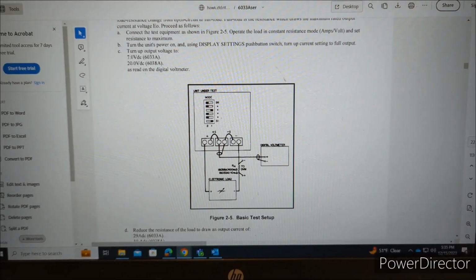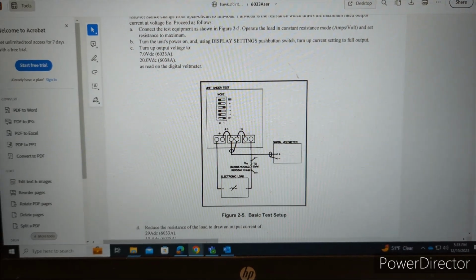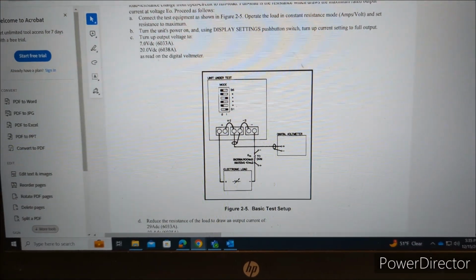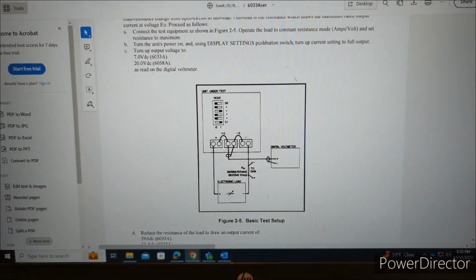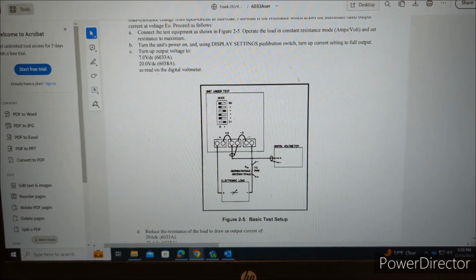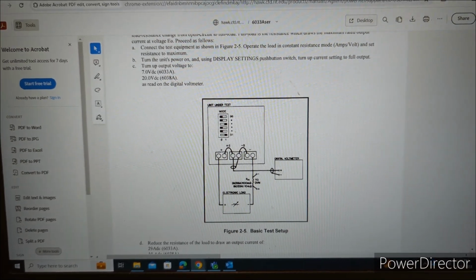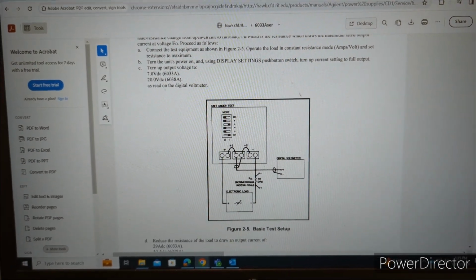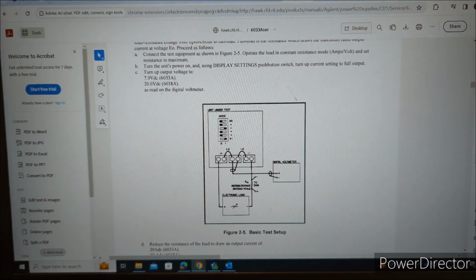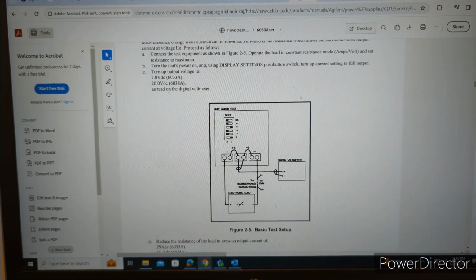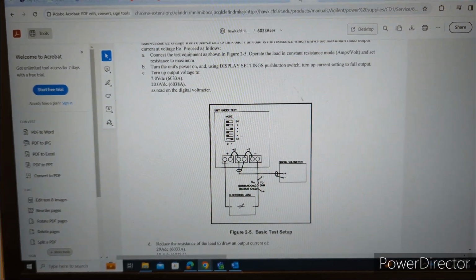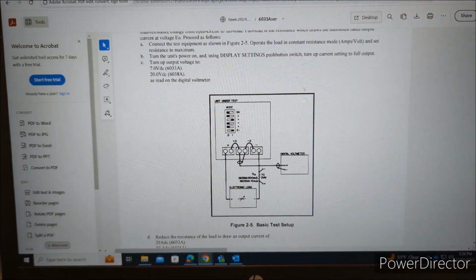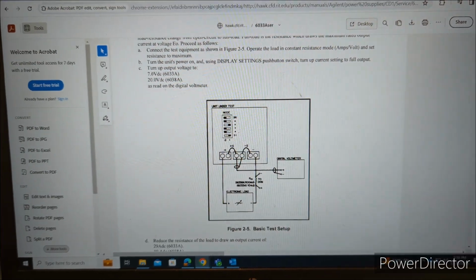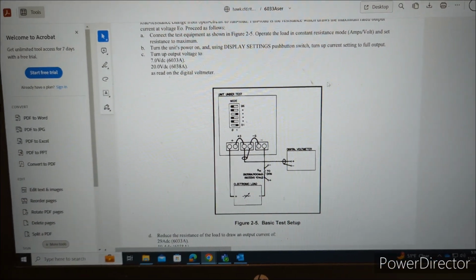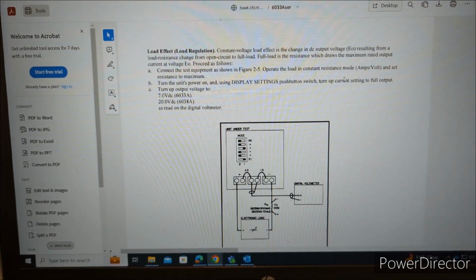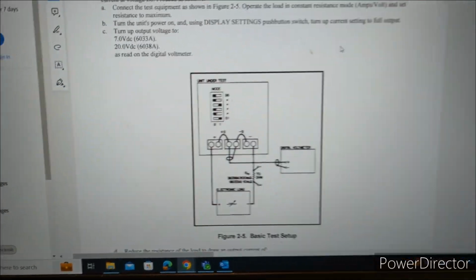Okay, so I figured we could do some performance testing now with the instrument after we've checked all those bias voltages, and it seems like everything is in good working order. And so I checked the service manual because it does have some performance test procedures. Now, as I said earlier, the calibration procedure is strictly done with the GPIB controller, and even some of the performance tests are done with that controller as well.